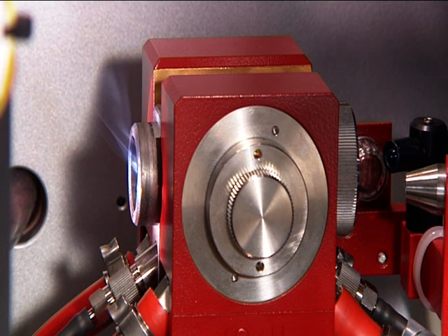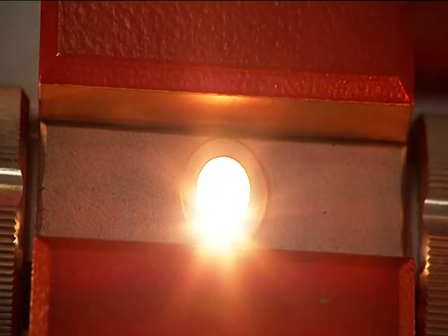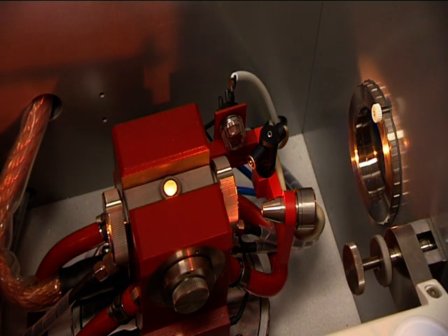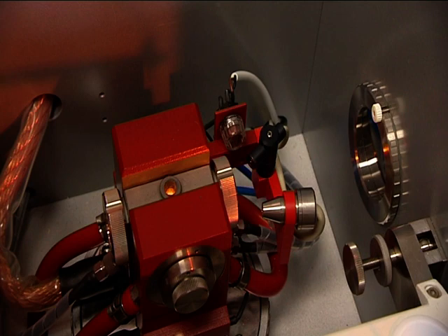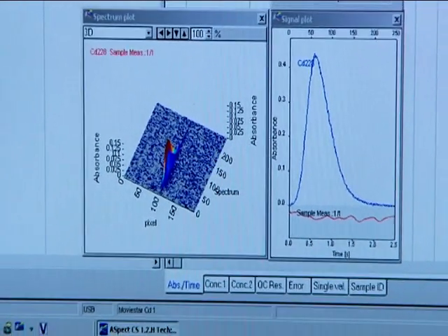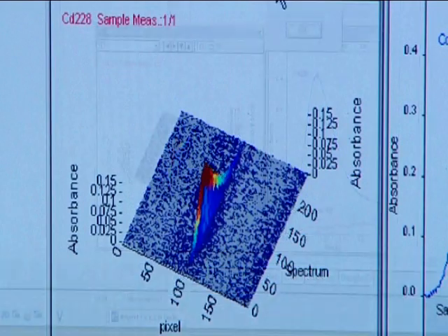The samples are measured out by hand on reusable graphite platforms. The robot arm of the sampler transports the platform to the integrated microbalance. Subsequently, modifier solutions and standard solutions or other reagents are added automatically and the sample is transported into the graphite furnace. After the measurement, the platform is immediately ready for the next sample. Due to the fully automatic measurement of up to 84 samples, the sampler makes a high throughput of samples possible.